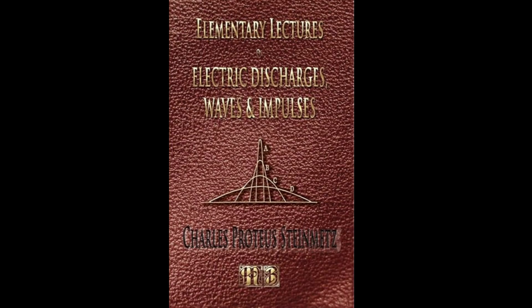A voltage, (μ minus 1) E0, must be induced in the field circuit by the transient of the magnetic flux. As a transient of duration L0 over R0 induces the voltage E0, to induce the voltage (μ minus 1) E0 the duration of the transient must be T equals L0 over (μ minus 1) R0, where L0 equals inductance, R0 total resistance of the field exciting circuit, inclusive of external resistance. The short-circuit transient of an alternator thus usually is of shorter duration than the short-circuit transient of its field, the more so, the greater μ, that is, the larger the ratio of momentary to permanent short-circuit current. In Figure 21 the decrease of the transient is shown greatly exaggerated compared with the frequency of the armature currents, and Figure 22 shows the curves more nearly in their actual proportions.